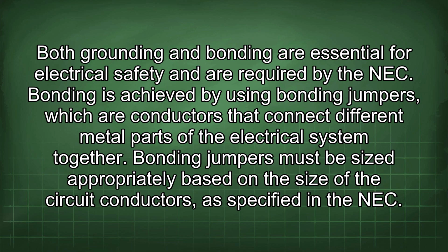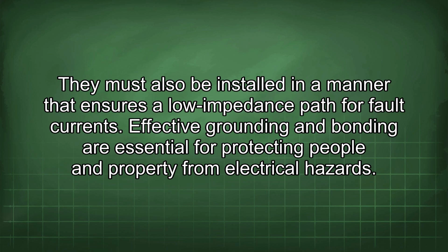Bonding is achieved by using bonding jumpers, which are conductors that connect different metal parts of the electrical system together. Bonding jumpers must be sized appropriately based on the size of the circuit conductors as specified in the NEC. They must also be installed in a manner that ensures a low impedance path for fault current.